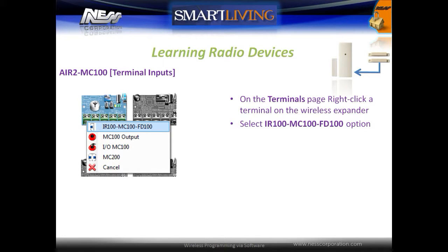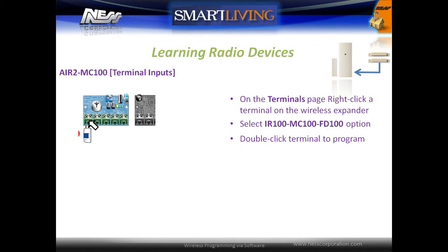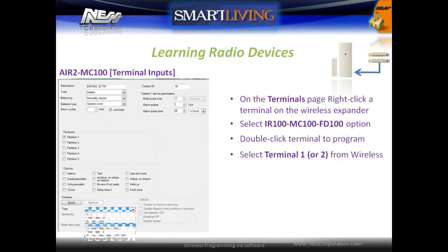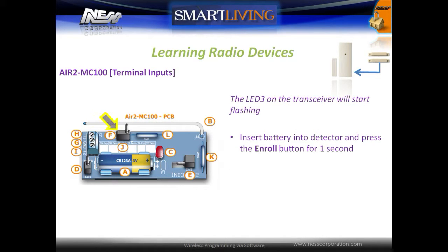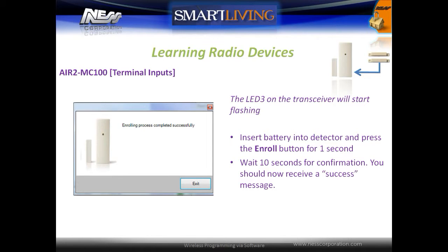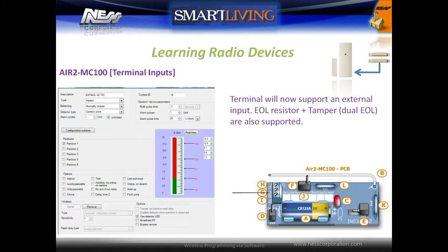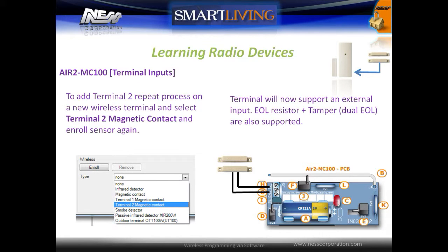To learn one of the reed switch's terminals as an input, on the terminals page right click on a terminal on the wireless expander, select the IR100 option, and double click to open the programming window. Under the wireless programming section, select the type as terminal 1 or 2. Click the enroll button, and once the system is in enroll mode the transceiver's LED 3 will start to flash — press the enroll button on the device. After about 10 seconds, a message should confirm that the device was enrolled successfully. The terminal will now support an external input and can also be configured for an end of line resistor plus tamper. To program the second input, repeat this process on a new wireless terminal and select the terminal 2 magnetic contact option and enroll the sensor again.